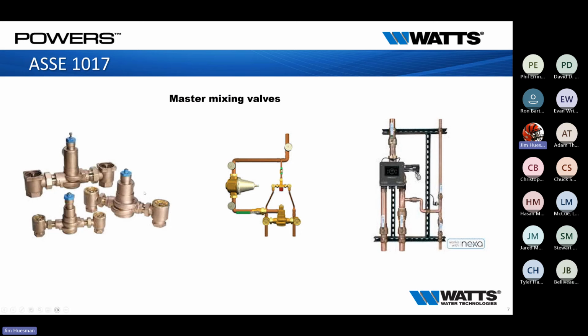When we talk about the operations of our master mixing valves, we can correlate that to how the internals work on our mixing valve here and our low flow here. I'll mainly be talking about how to set our temperature on the low flow and high flow, and then why that PRV is there - what is it doing, since it's not made for mixing water, it's more for pressures. We'll discuss how this operation all works. Once dialed in, it works great, but it's very, very time consuming.